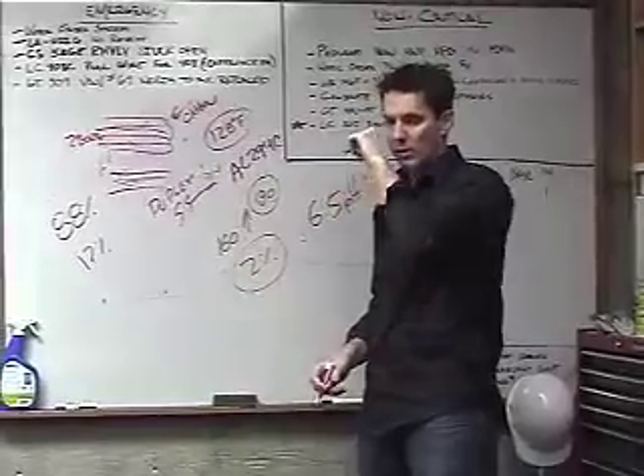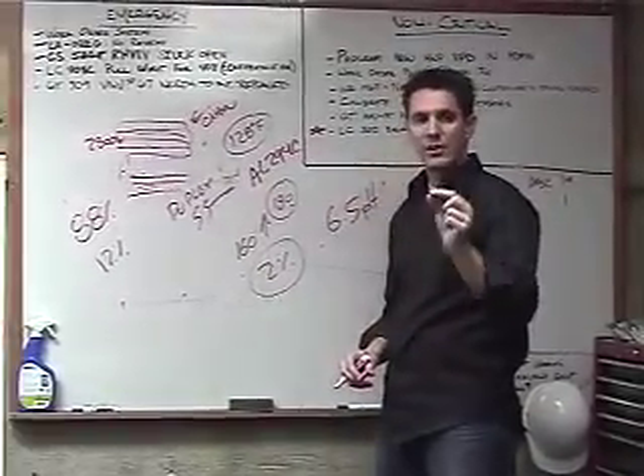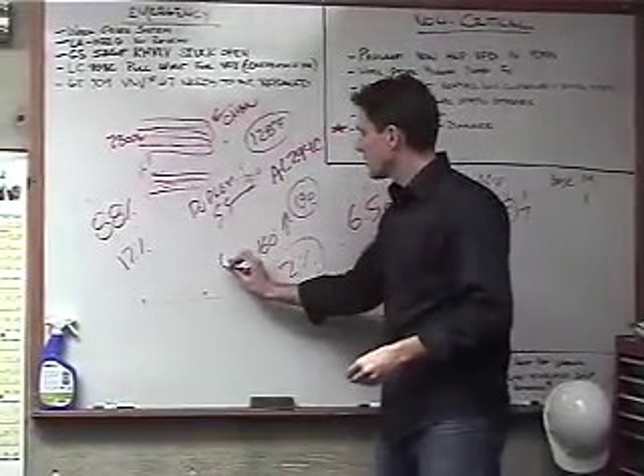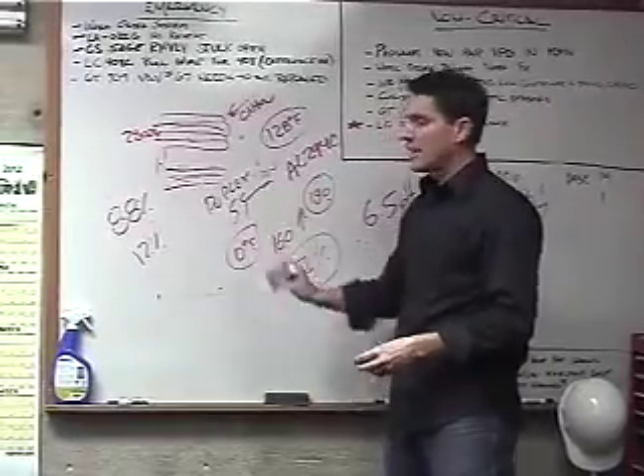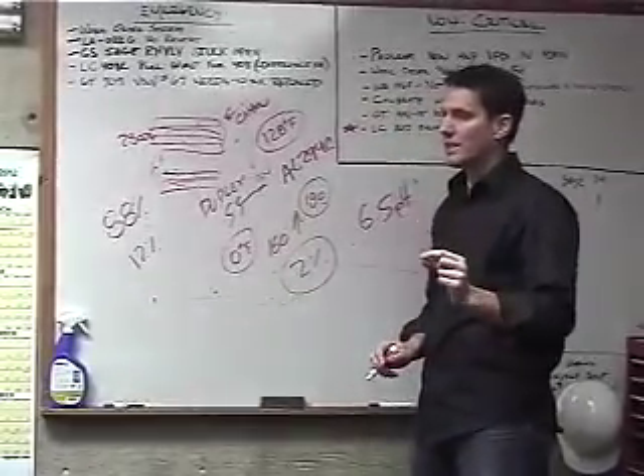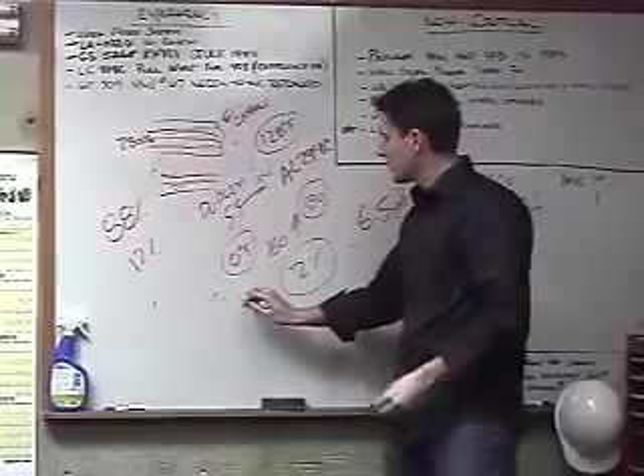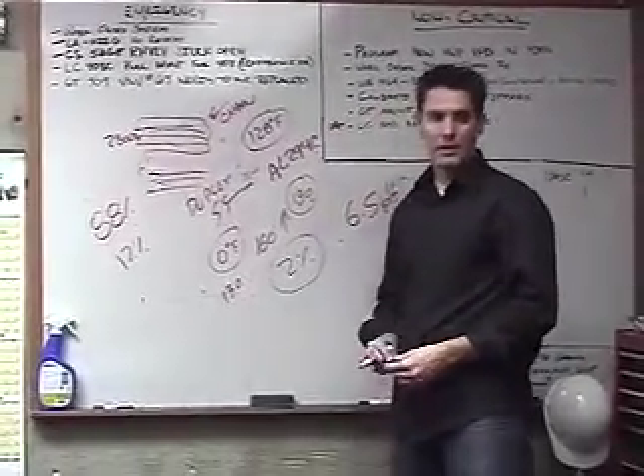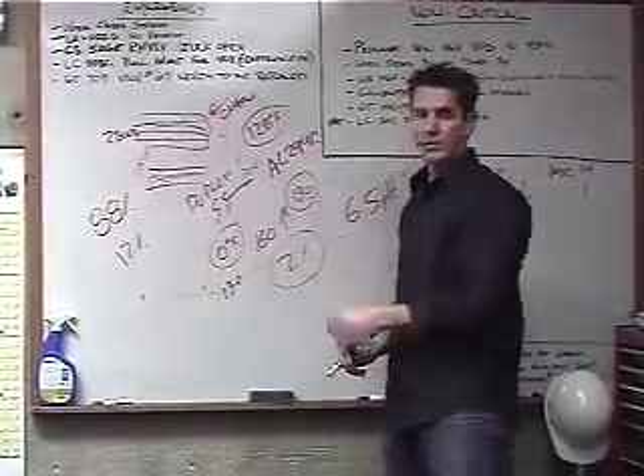I've got an engineer I work with out of Indianapolis. 100% of his job, their design temperature is 0 degrees. So the coldest day of the year is 0 degrees. And every school that he does, on the coldest day of the year, he supplies 130 degrees Fahrenheit. So he's always condensing, even when it's really cold outside.